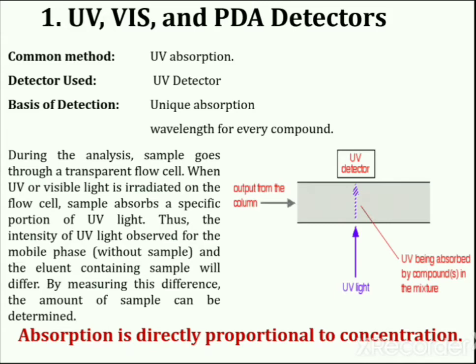PDA detectors detect an entire spectrum simultaneously. UV and visible detectors visualize the obtained result in two dimensions — light intensity and time — but PDA adds the third dimension: wavelength. So with UV visible and PDA detectors, it is convenient to determine the most suitable wavelength without repeating the analysis.